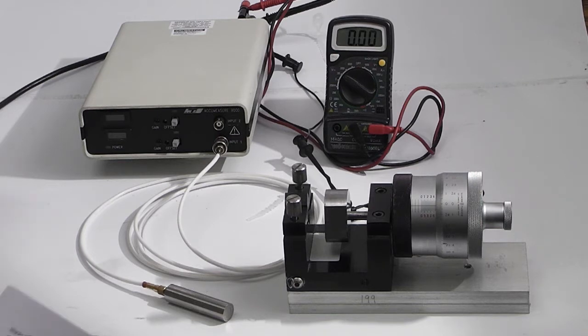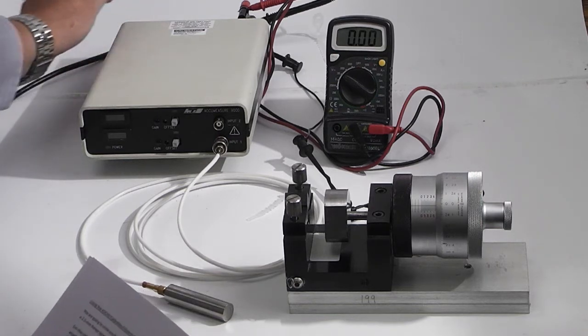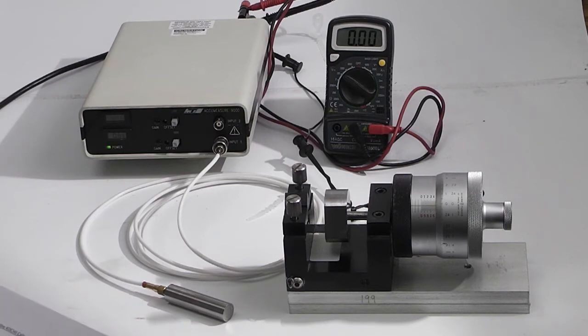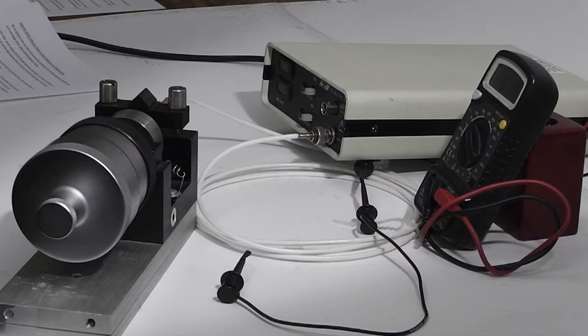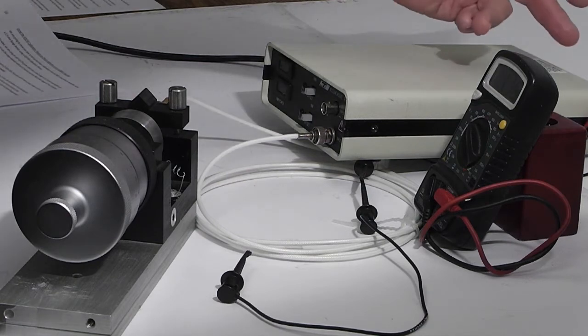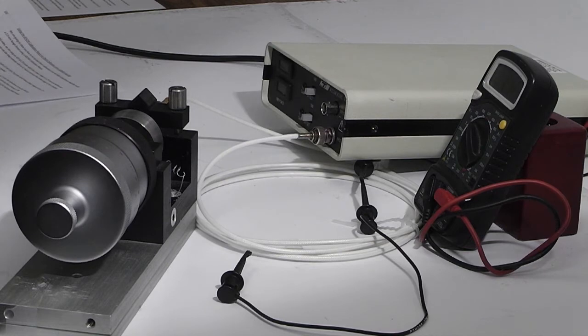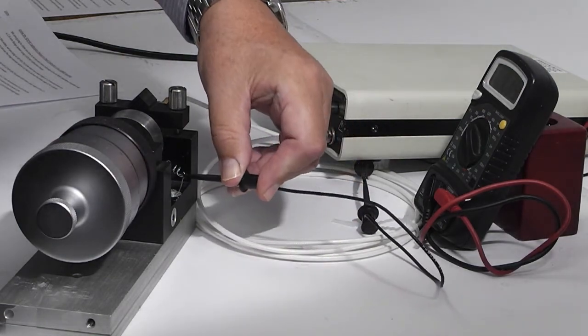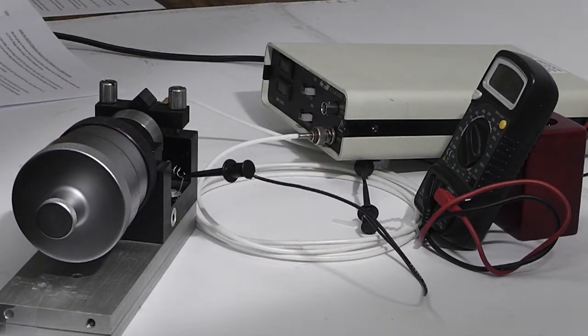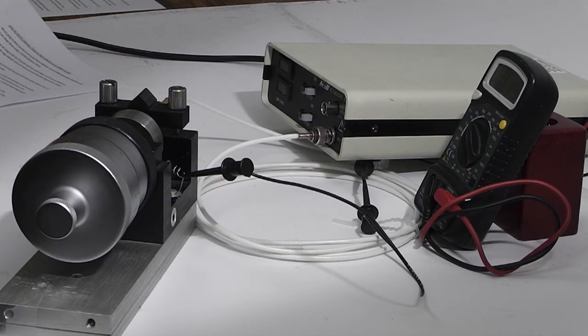First, we'll turn on the AC power switch on the AS9000 amplifier and allow it to warm up for 15 or 20 minutes. A ground clip is connected from the rear panel ground banana jack on the back of the amplifier, and the opposite end is connected to the ground connection of the calibration fixture. This ground clip is needed to complete the ground path circuit back to the AS9000 amplifier.